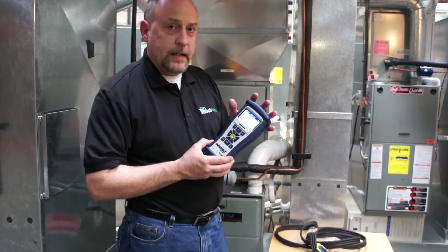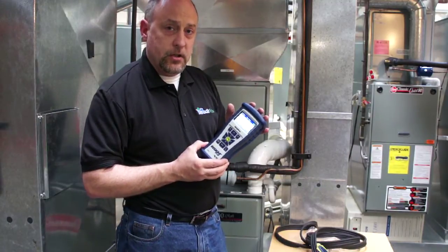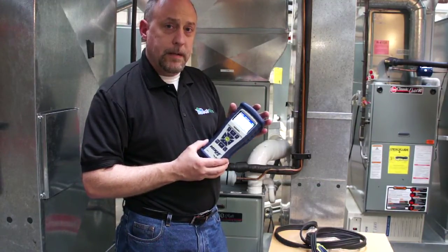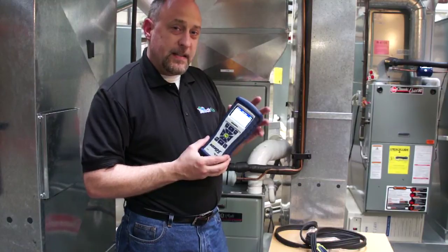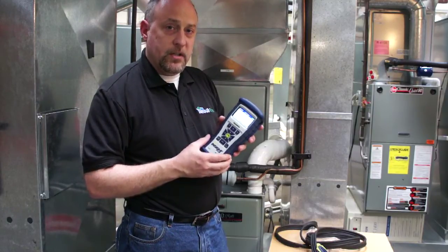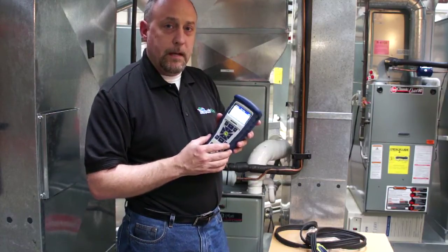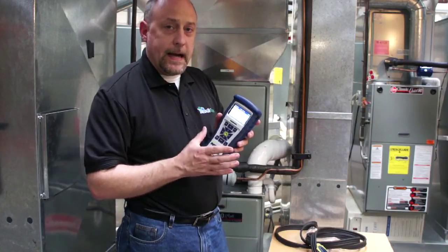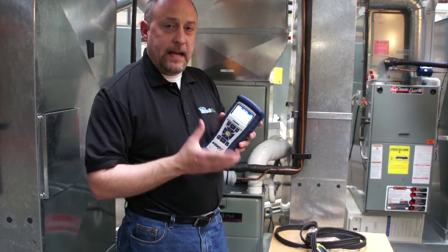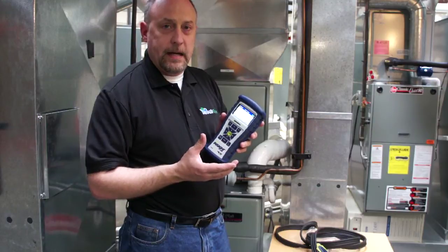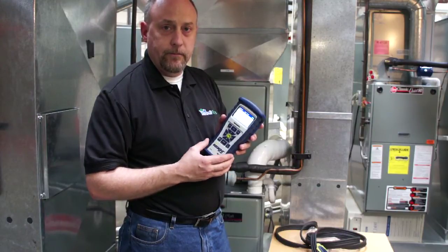Another really cool thing they did is they actually went to a higher range sensor. So now the instrument contains a 4,000 ppm sensor. And what they did that's unique is they calibrated it at the low end of the range. So the sensor is calibrated with about 200 ppm CO gas. So you get really high accuracy in the low end of the range, but you get that extra protection at the high end range of the instrument.